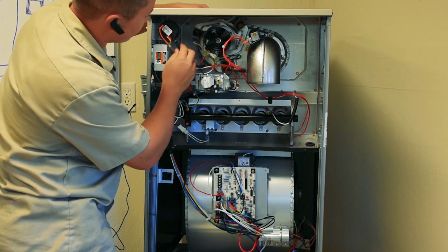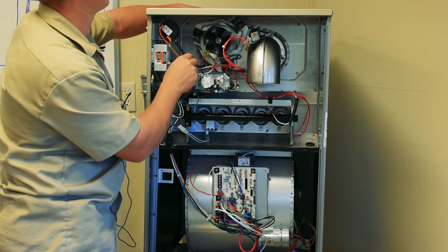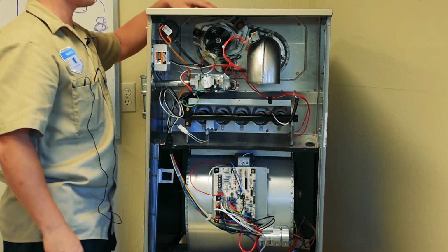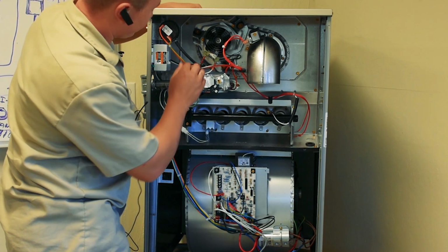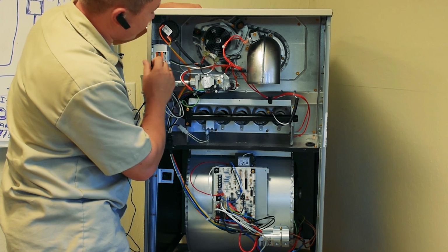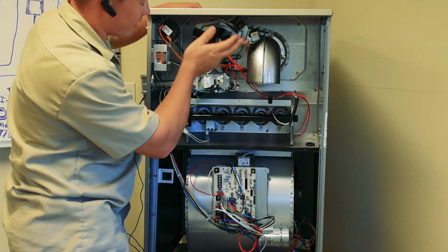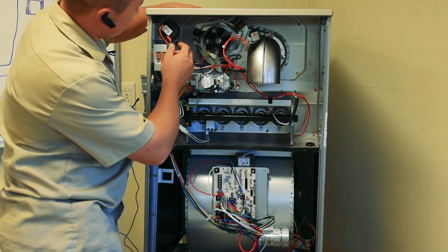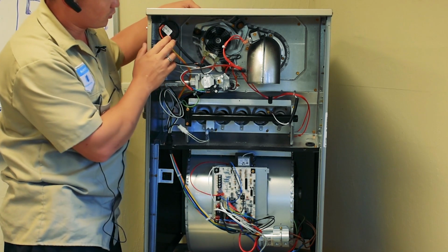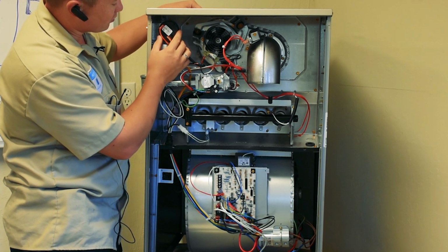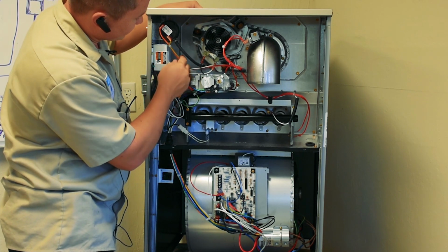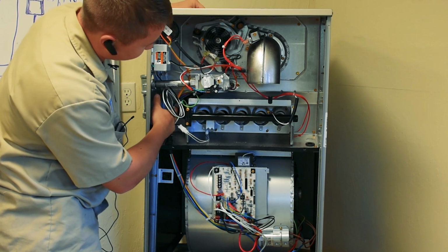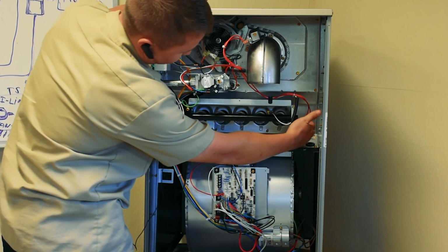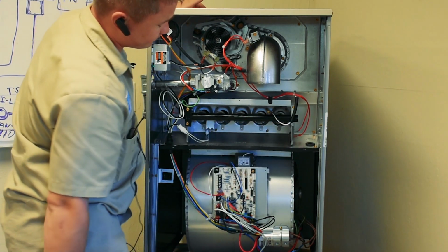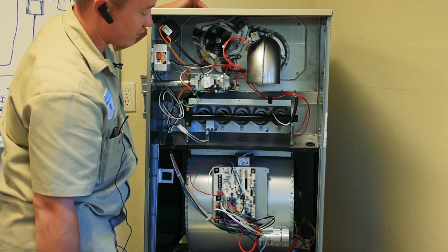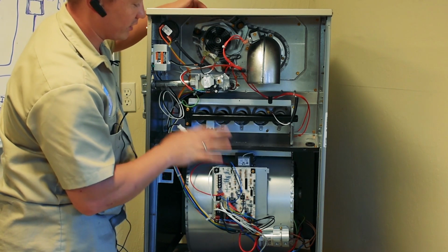Here we have a pressure switch connected to this heat exchanger collector. Because it's sensing the decrease in pressure, since it's removing the air from the heat exchanger collector, this pressure switch, on this model, is normally open. It's closing this circuit, which is also connected together with the safety thermostat. On this model it's right here and right here, because that thermostat is responsible for the safety of the furnace against overheating.